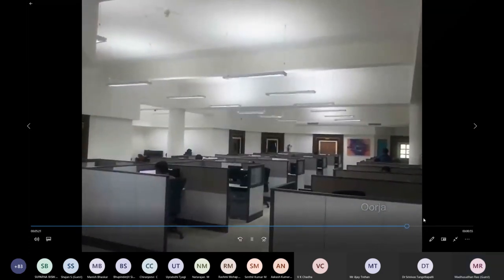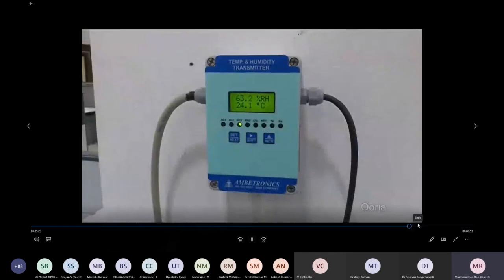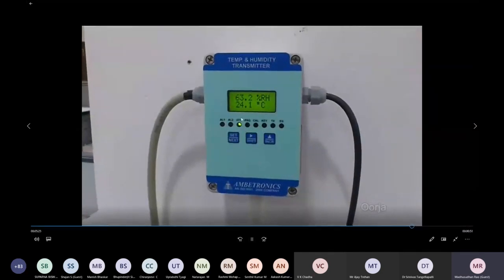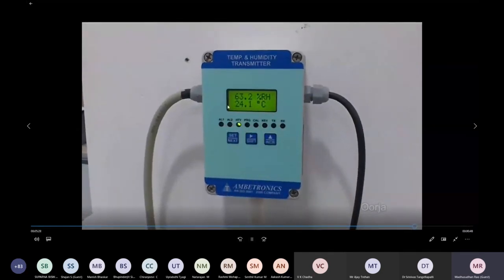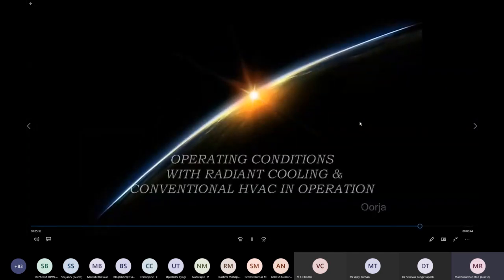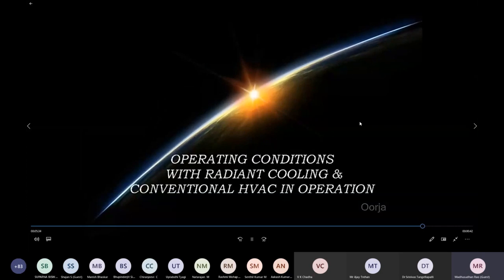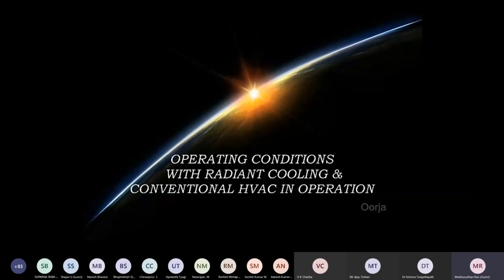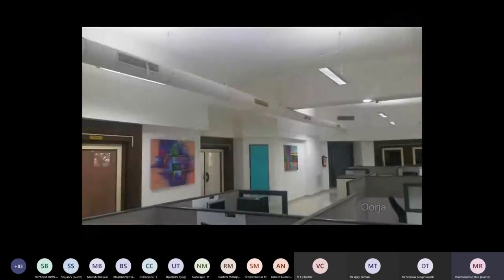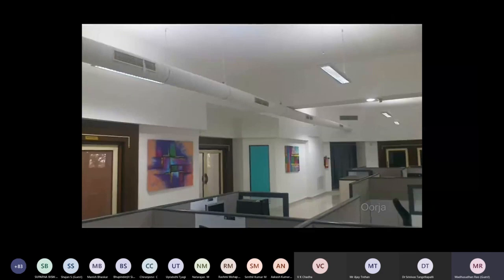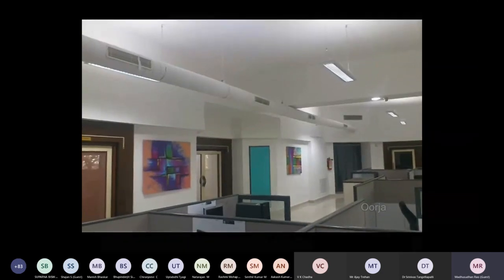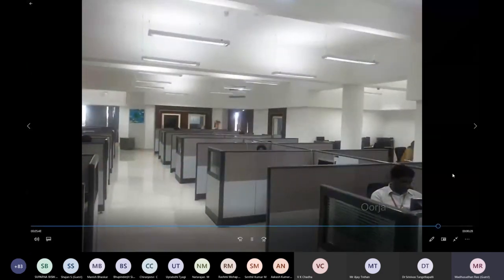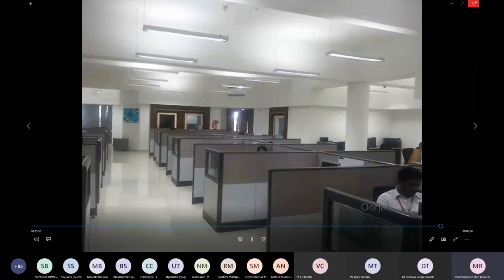You will see that by running only the radiant cooling system, we were able to achieve the desired temperature, but not the RH. Therefore we do require an air system to control the humidity in the air. If it's a property of the air, then I need an air system, but that is significantly lower, usually about 10 to 15%, depending on the location.